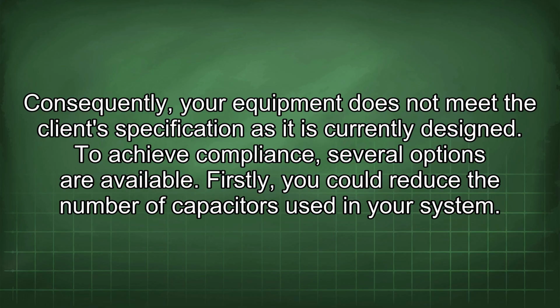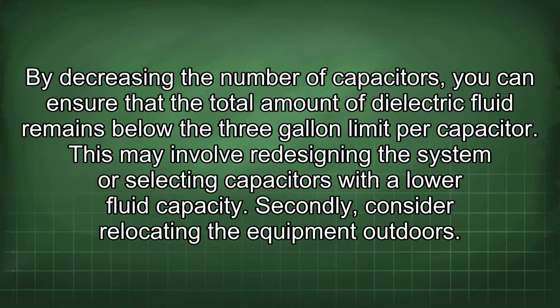To achieve compliance, several options are available. Firstly, you could reduce the number of capacitors used in your system. By decreasing the number of capacitors, you can ensure that the total amount of dielectric fluid remains below the 3-gallon limit per capacitor. This may involve redesigning the system or selecting capacitors with a lower fluid capacity.